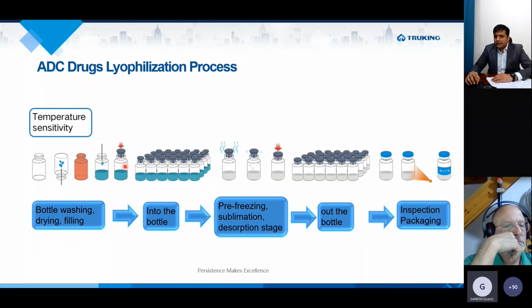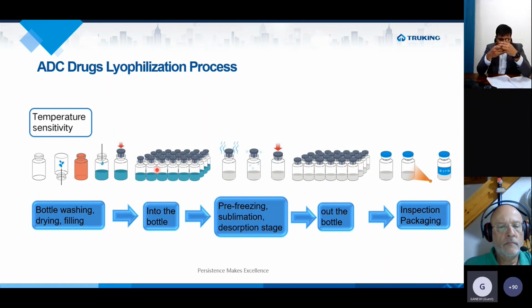Then, under aseptic conditions, it is transferred to a freeze dryer, which can automatically load the containers row by row or using an AGV inside the machine. After that, lyophilization can majorly be described as a three-step process. First is freezing, then primary drying, then secondary drying, where the sublimation and desorption happen, and the liquid directly transforms into dry powder. Then the freeze drying process is complete.